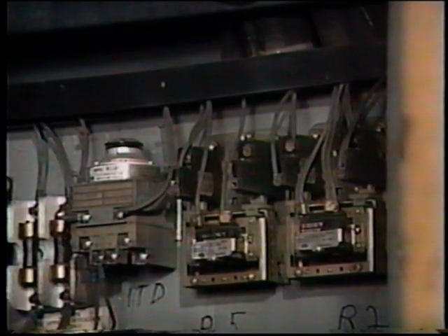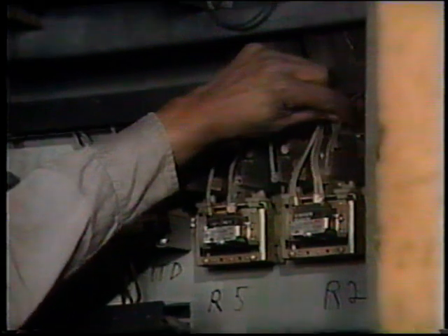It's important to clean the controller as completely as possible. Dust, dirt, or other contaminants may contain conducting materials that can cause short circuits and grounds inside a controller. Dirt may also prevent contacts from closing properly, and an incomplete circuit could result. Once the controller is cleaned, examine its wiring.